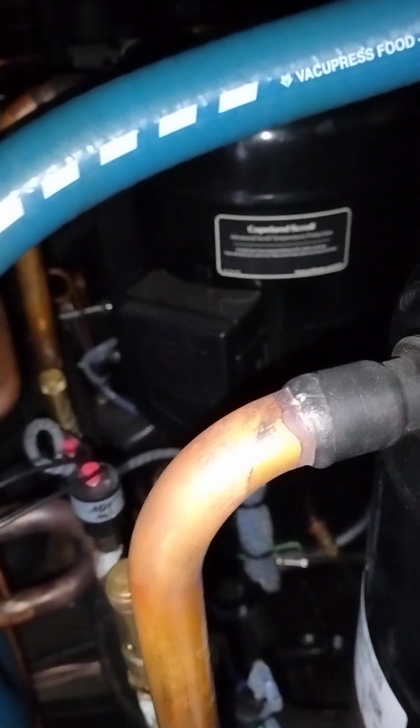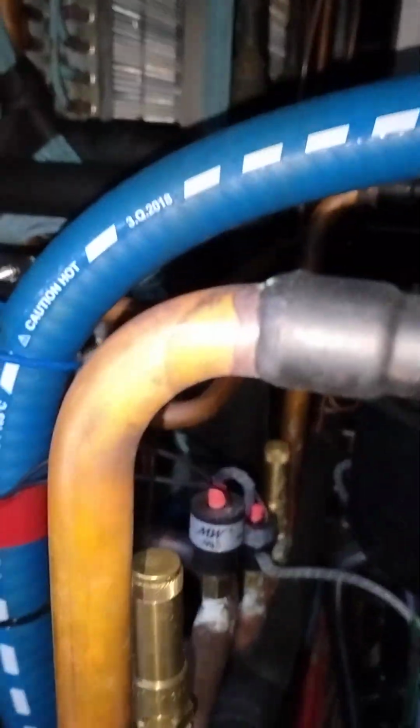So in order to replace, for instance, one of these compressors, the front one is maybe simple, but for the back one you have to open that back panel, which means you need back access. So it's not a nice design, to be honest. But since we're here, let's go over the typical path for the refrigerant.